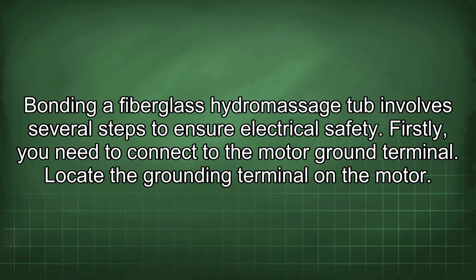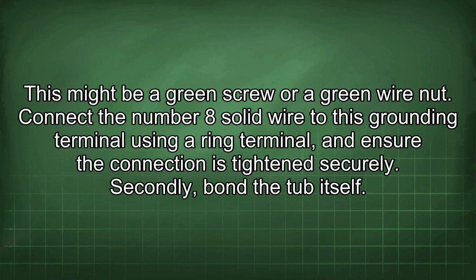Bonding a fiberglass hydromassage tub involves several steps to ensure electrical safety. Firstly, you need to connect to the motor ground terminal. Locate the grounding terminal on the motor. This might be a green screw or a green wire nut. Connect the number 8 solid wire to this grounding terminal using a ring terminal and ensure the connection is tightened securely.